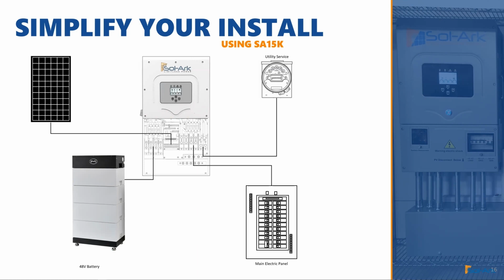On the AC side, you go directly from your utility meter through an AC disconnect - that's both code, and because our inverter is not service entry rated. You go through a fused AC disconnect, land that directly on the grid side of our inverter, and then we can power out of our load output, which is the circuit we can provide backup power on, taking that circuit directly to the main lugs of the home service panel. So there's no more need for a critical load subpanel.